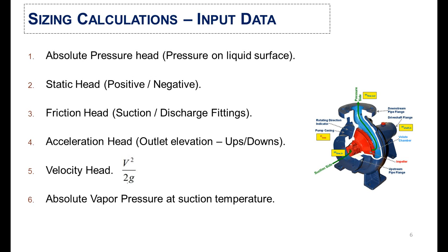This is the basic input data required to proceed with the sizing calculations. You will require the absolute pressure head, which is the pressure on the liquid surface, the positive or negative static head, and the friction head, which comes from suction and discharge fittings across the pump, such as strainers or non-return valves (NRV).